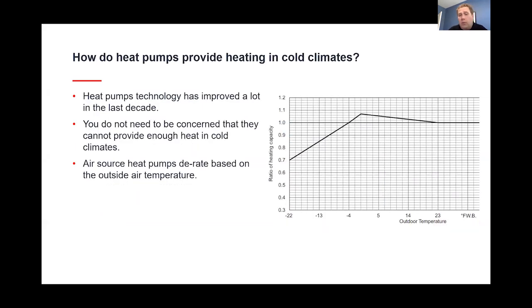And to produce the heat in the winter, heat pumps have to absorb heat from the outside air. As the air gets colder, there is less heat to be absorbed. This is what we call derates, and it's important to size your system with the proper ambient temperatures. And technology really has come a long way from what some of you may be used to in terms of the derates. So no longer do you have to be concerned with severe derates on products like VRF and mini splits. And this chart is an example of a VRF system that you can see at negative 22, it still provides 70% heating capacity.